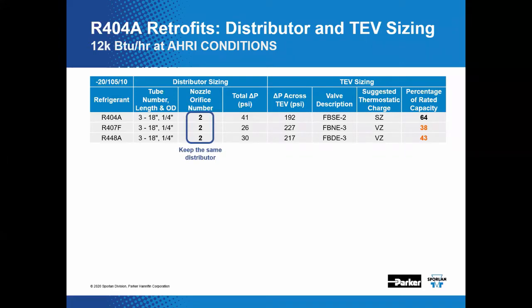Let's start by assuming we want to keep the same distributor orifice. That yields distributor total delta P's that are lower than for R404A, but still acceptable. Now, instead of 192 psi drop across the TEV, we're going to 227 or 217 psi. We'll see how things look if we also keep the same TEV. But wait, those aren't the same TEVs for 407F and 448A.